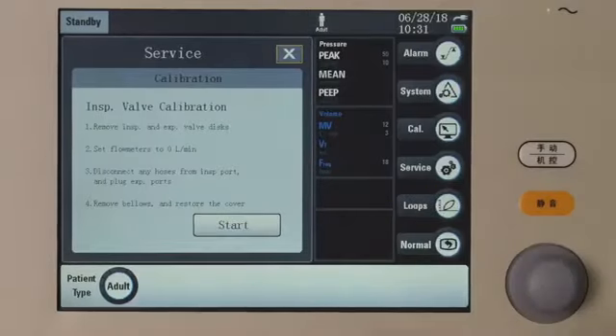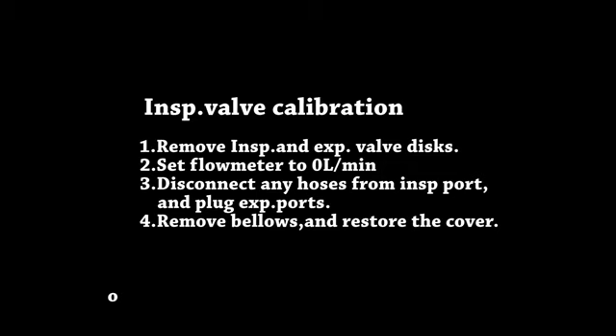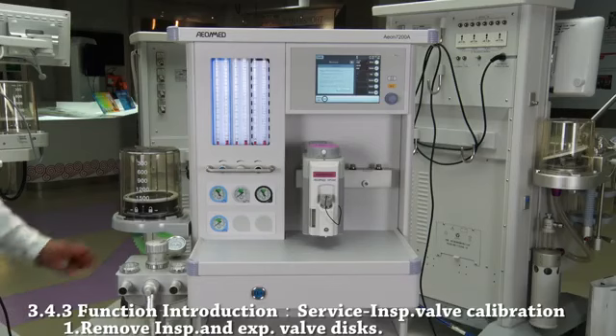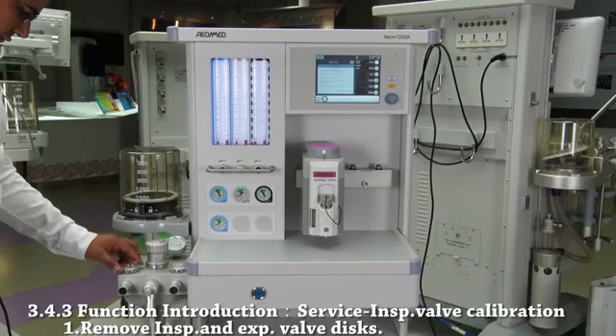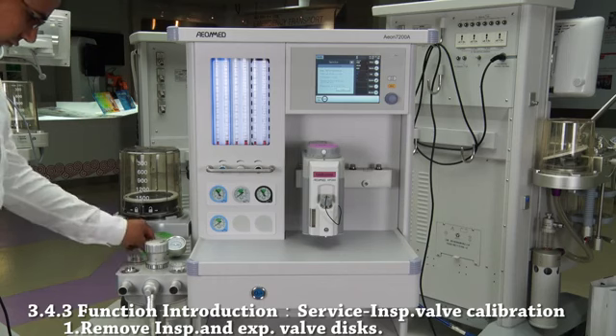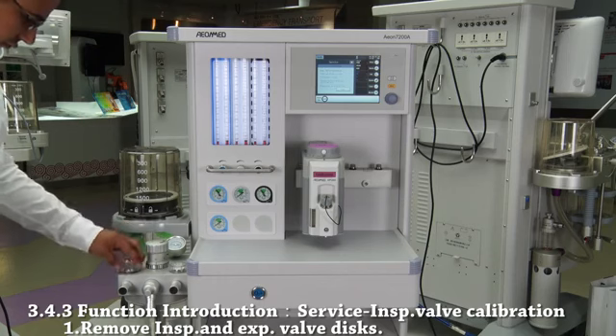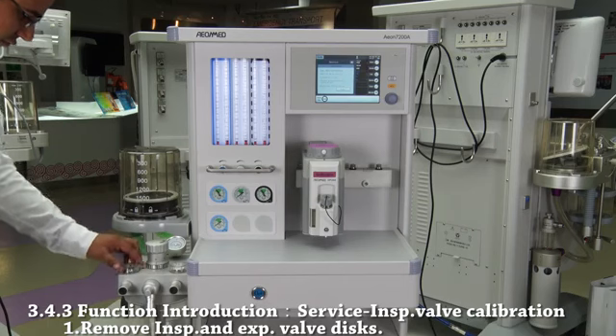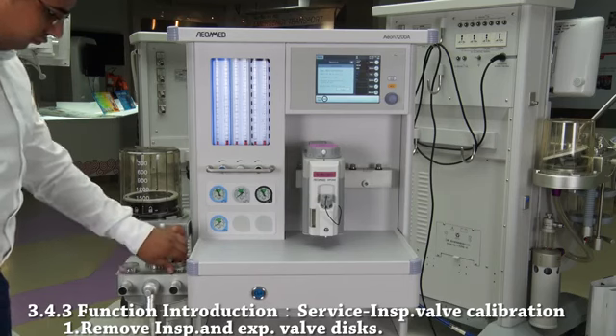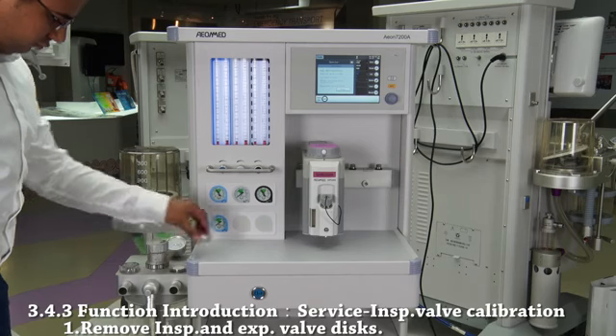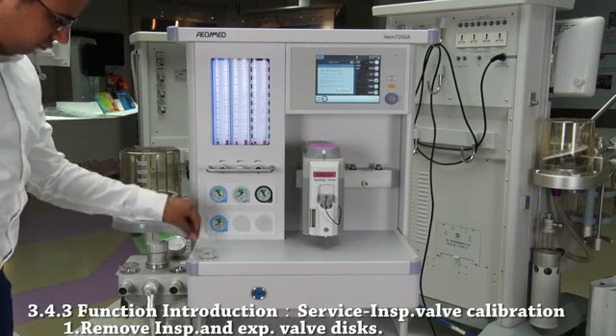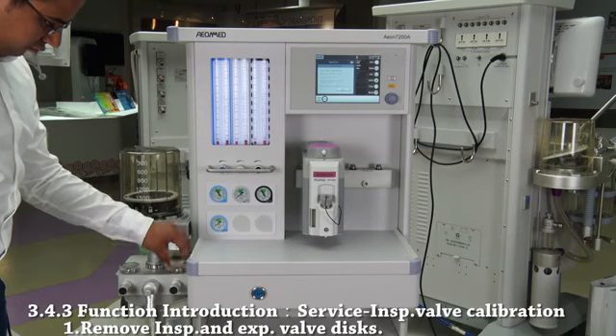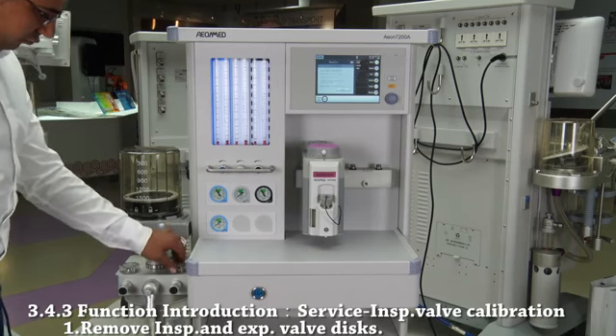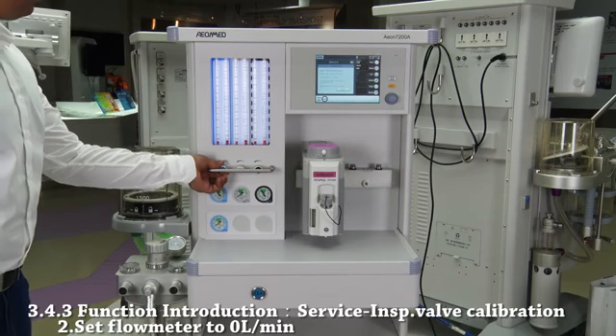Press here for inspiratory valve calibration. Step 1. Remove inspiratory and expiratory valve discs. Step 2.